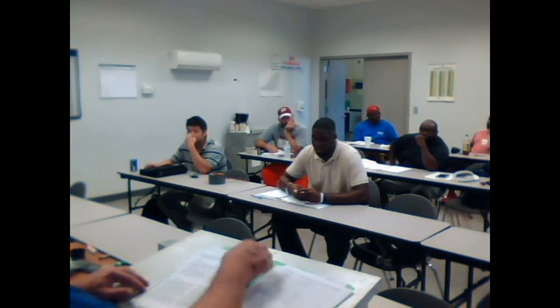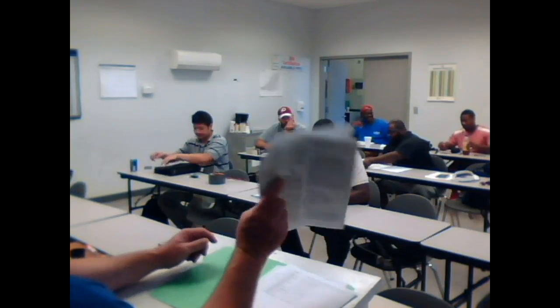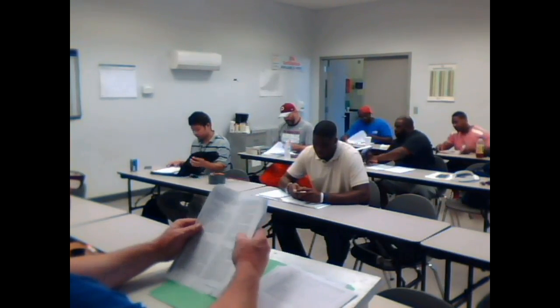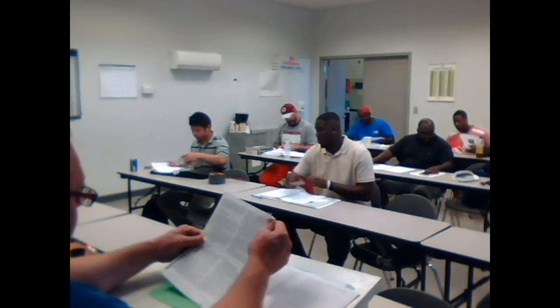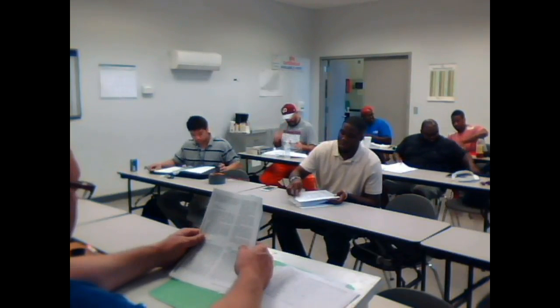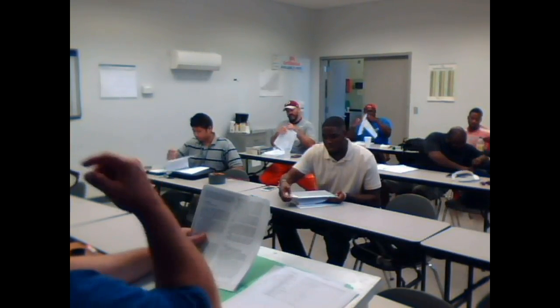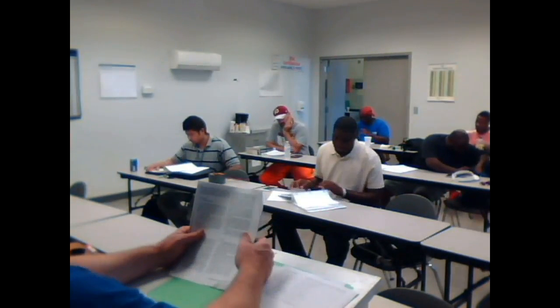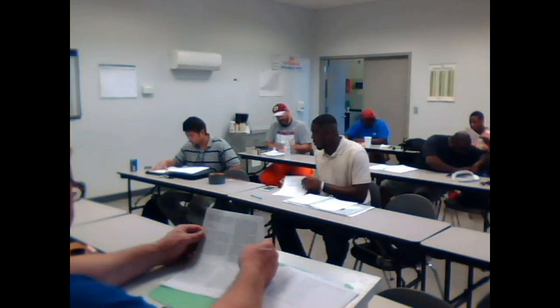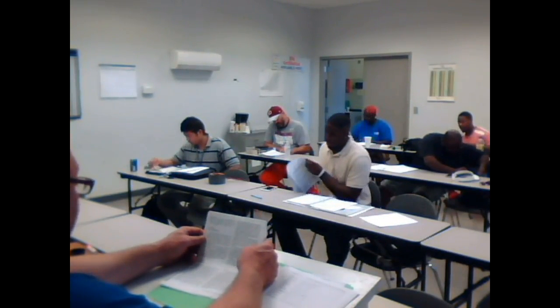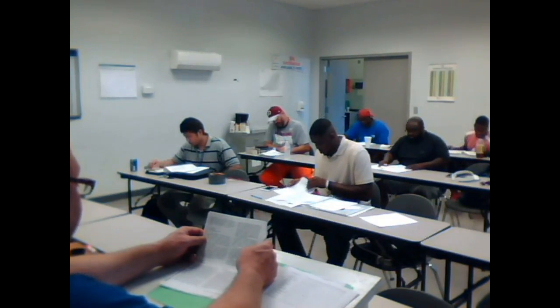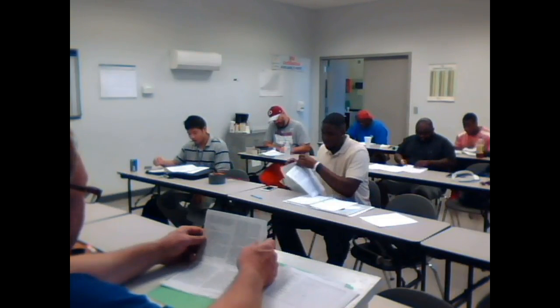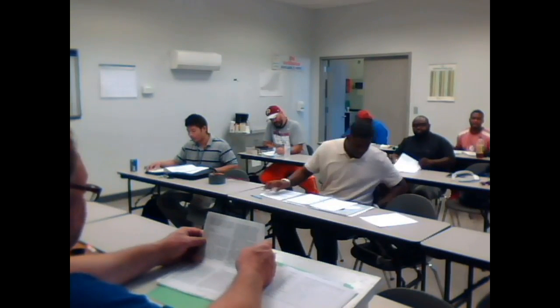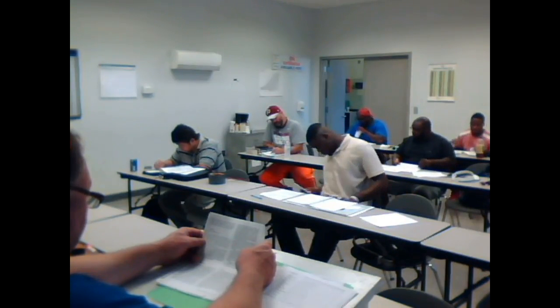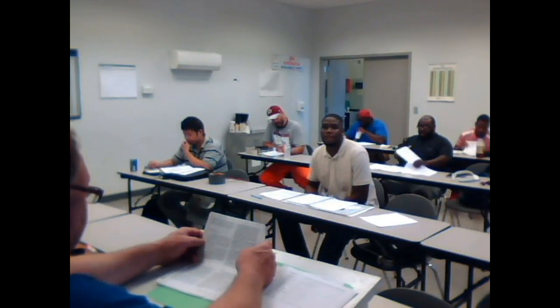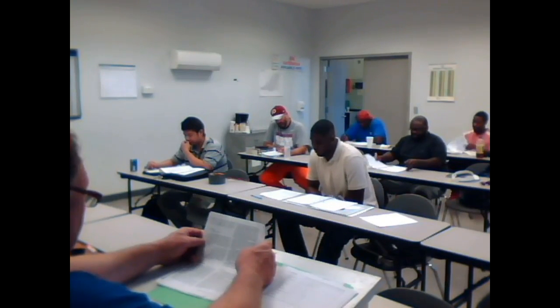Okay, so I'm going to start here on page 305 of that handout I gave y'all on voltage high. Voltage high. We talked about that if it's single phase, we have a tolerance of plus or minus 10%, right? It says at no time should the voltage supplied to a condensing unit be higher than 10% of the normal voltage rating of the unit. Therefore, a 240 volt unit, the maximum applied voltage should not exceed 264 volts. Higher voltage than normal subjects the unit to higher current draw with attendant damage.